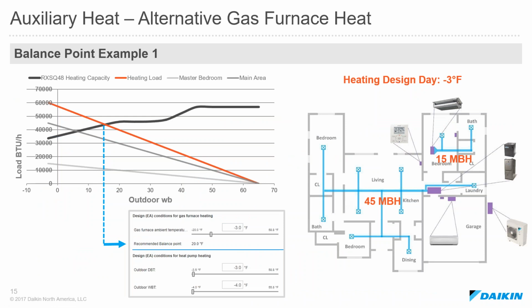So let's look at some numbers. That same example, just throw some numbers to that example. We have a heating design day temperature of -3 degrees outside, a 45 MBH load for that main common area, that gas furnace and A coil, and then we have a 15 MBH load for that master bedroom. So the total load line is that red line there. It's a sum of those two, and that occurs at -3 degrees outside. And that's going to intersect a 4-ton capacity curve at around 16 degrees.